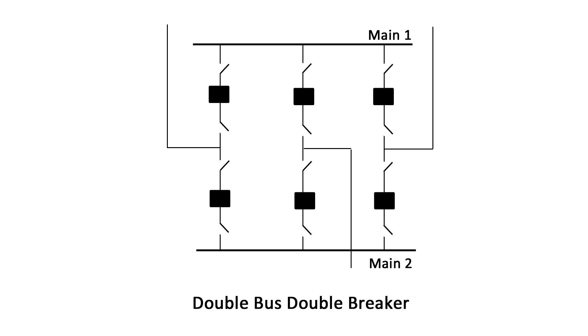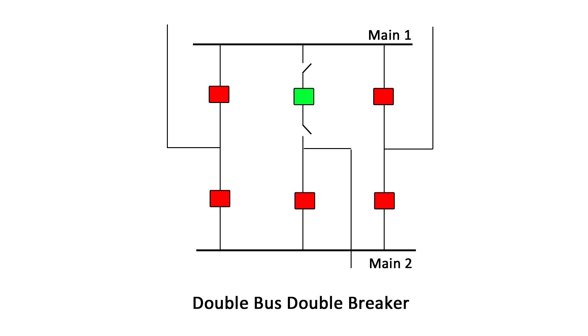Number 3. Double bus, double breaker. The double bus, double breaker configuration utilizes two buses and two breakers per circuit. Both buses are normally energized and any circuit can be removed for maintenance without an outage on the corresponding circuit.